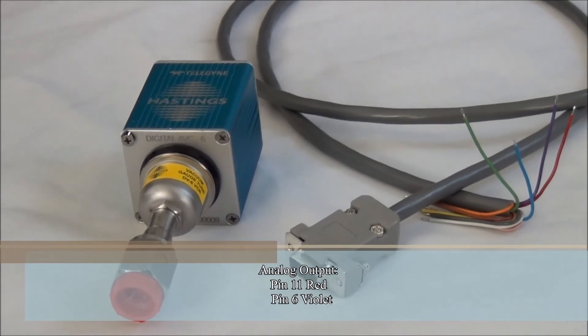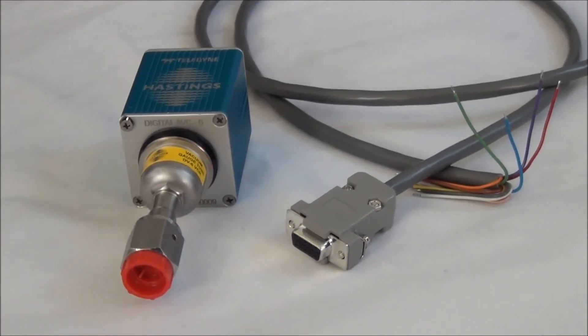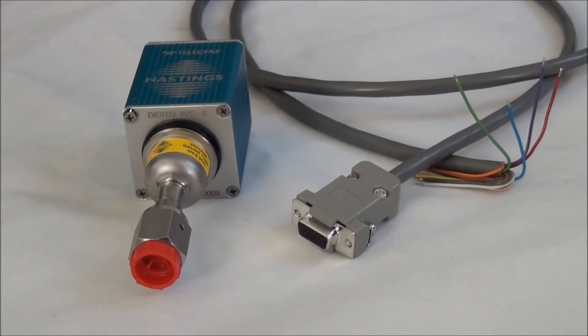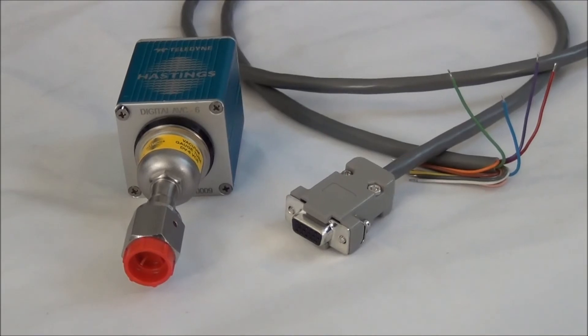I'll point out again that the DAVC can be configured to give 4 to 20 milliamp output. Now 4 to 20 milliamp can be very useful in electrically noisy environments or when the DAVC is mounted far from a PLC.